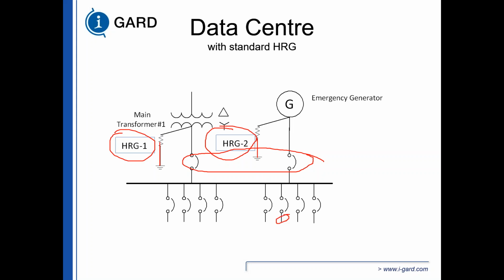The fault is down here. This is where the fault is. The return path is either going to be the transformer if this breaker is closed, or it's going to be the generator if this breaker is closed. So the operator, the maintenance people looking at this system are going to have to look at two different locations to determine if they have the ground fault, depending on whether the transformer is supplying power or the generator is supplying power. And sometimes the generator is going to be in a far further location because you don't want to have all that noise inside your data center. So you have to look at a different panel to determine if you have a ground fault in a data center.